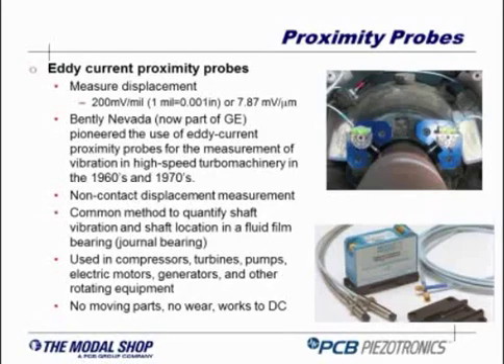And once it goes through a little box, a little power supply, what you get out of those transducers is a voltage output that's approximately 200 millivolts per mil. A mil is one thousandth of an inch. If we translate that to metric, we are talking about 7.87 millivolts per micrometer. So those sensors can measure really tiny gaps, and because they are non-contact transducers, they can be mounted directly close to the shaft that is rotating.